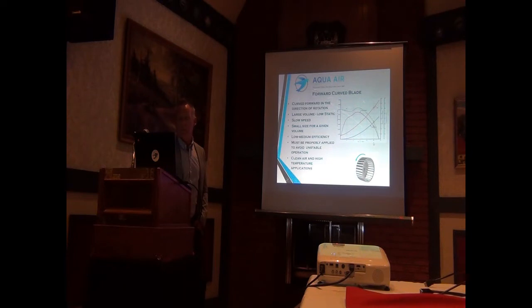Another important thing when you're calculating your external static pressure is to make sure those numbers are right, because if it sneaks up the side of the line and you get to the top, it could end up surging. If it gets down on this side, the fan will speed up, slow down, speed up, slow down, because they are overloading, they speed themselves up. In severe cases, if it's unchecked, your static pressure continues to rise and the fan will speed up, kind of like running down a hill. It just can't stop itself. It could fail, a complete failure of the fan. So it's very important that you get this selection correct. It must be properly applied to avoid unstable operation, for clean air and high temperature applications. You'll still see these forward curve fans sometimes in furnaces and all over the place.